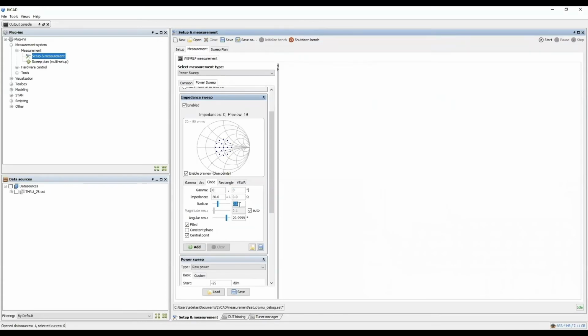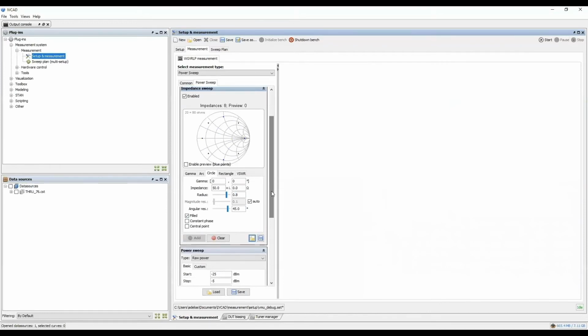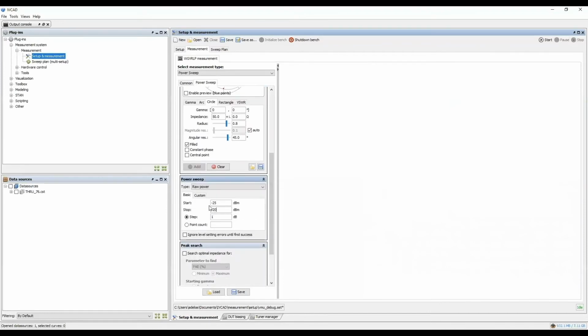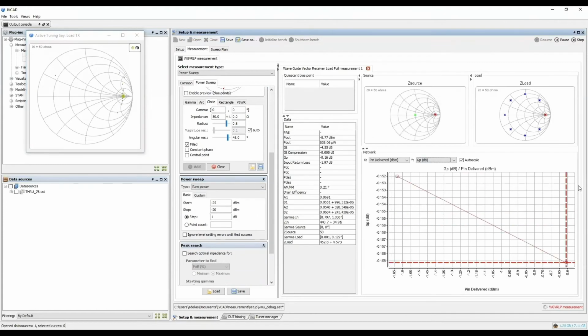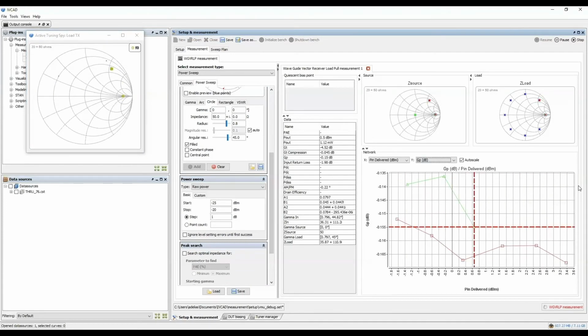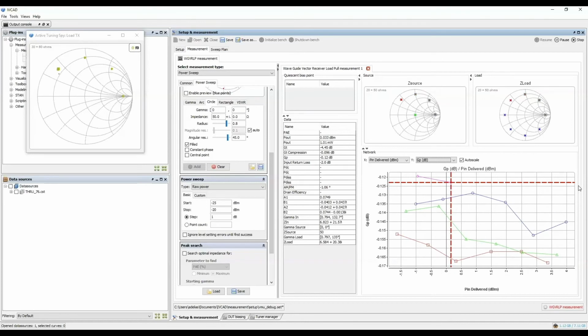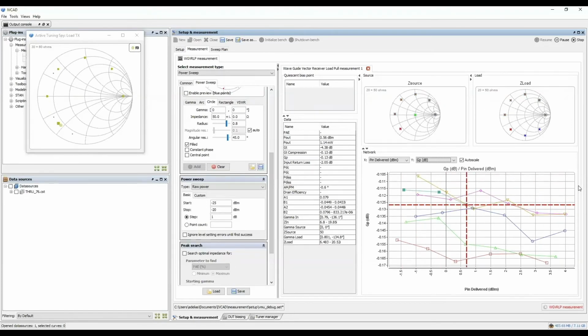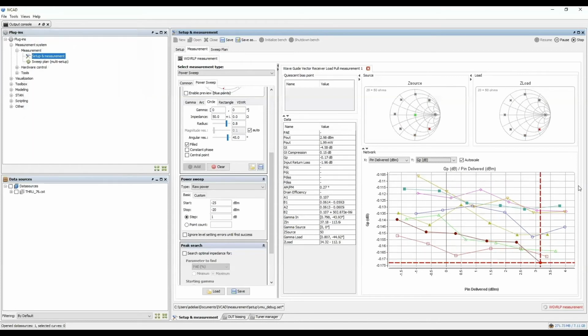Before we measure our DUT, we need to validate our calibration. For vector receiver load pull, the validation parameter is power gain on a through connection, and we are looking for something less than plus or minus 0.2 dB at all phases of 0.8 gamma magnitude. In this case, our minimum power gain is minus 0.175 dB, which highlights a good system calibration.